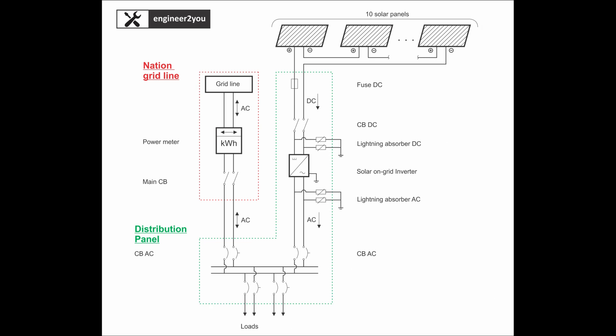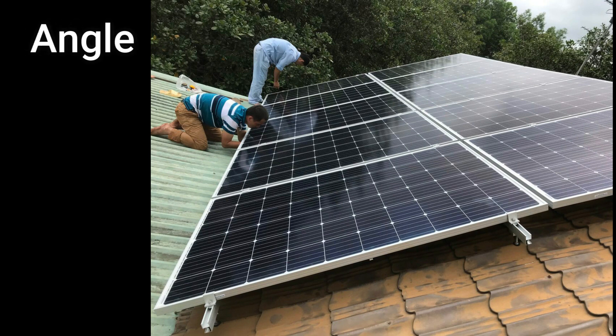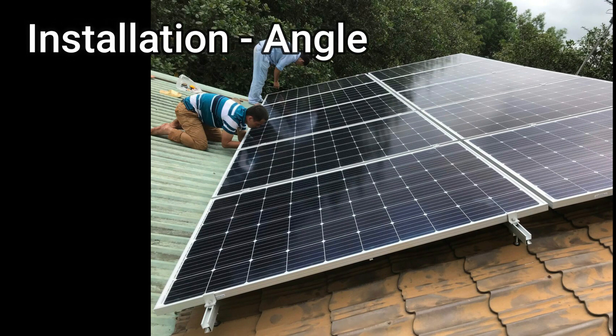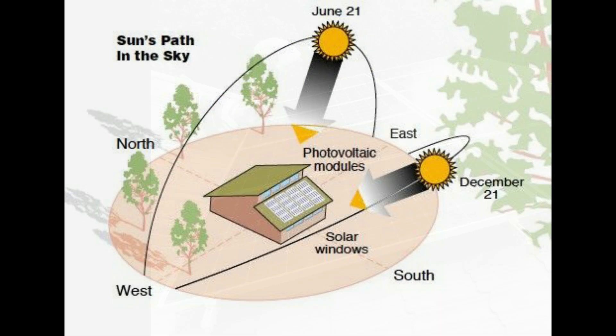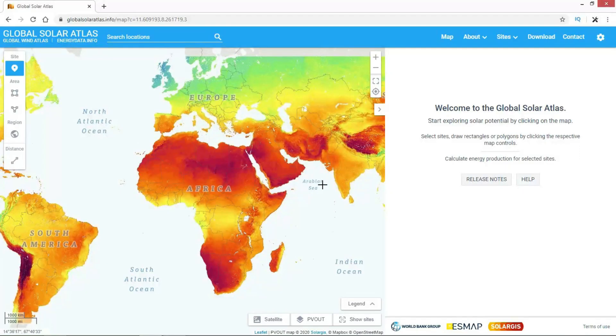After understanding the single line diagram, we make the connection diagram. In the next section, I will tell you how angle of installation can affect total producing power. Because of Earth's axis, most of the time in the year we will get more sunlight from the south direction, so it's better to orient installation toward the south. To find the exact installation angle for your location, go to the Global Solar Atlas website and choose your location.